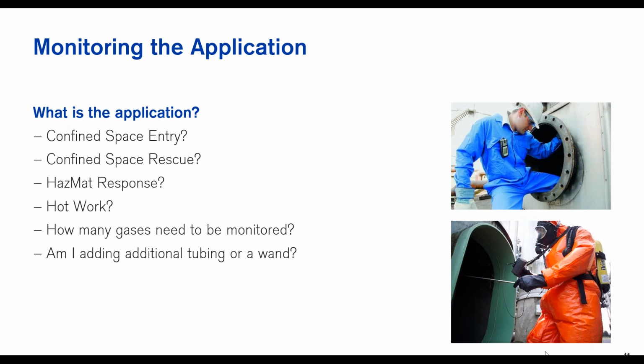So if we were going into a confined space, and let's say we had a nitrogen leak we were using for purging that system, even though it's an asphyxiation hazard, the meter would make you think you have a flammable environment when you don't. This type of detector does have a purpose in gas chromatography, but that's about it. We'll talk a lot more about that in the next webinar series.